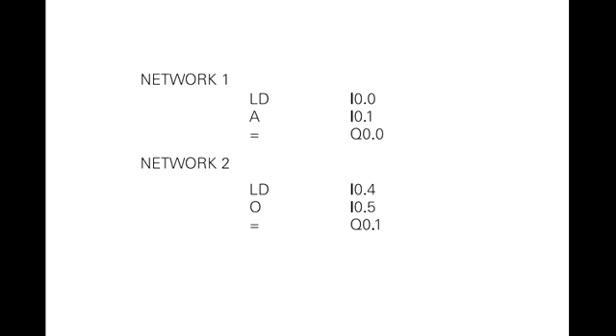Statement list. A statement list, STL, provides another view of a set of instructions. The operation, what is to be done, is shown on the left. The operand, the item to be operated on by the operation, is shown on the right. A comparison between the statement list shown below and the ladder logic shown on the previous page reveals a similar structure. The set of instructions in the statement list perform the same task as the ladder diagram.